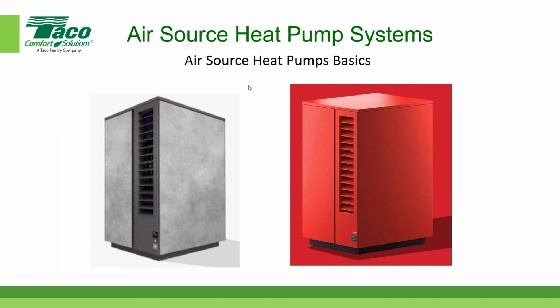downstream. Again, the higher the water temperature, the less surface area you need downstream. And for retrofit purposes, if you had a unit that could generate 160-degree water versus 140-degree water, you may be able to use that as a direct replacement for a boiler. So yeah, there are all kinds of things out there being explored for refrigerants and stuff like that. Very cool, but scary. I'm glad I'm old.